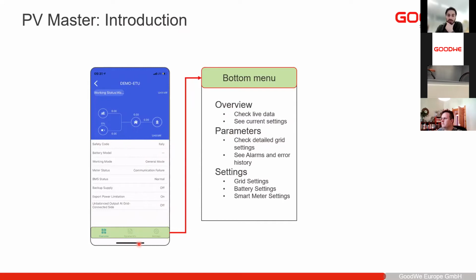Under parameters, you can check more details, what settings you have chosen, and you can also see the alarms and the history of the inverters. If anything happened, like there's a communication fault or grid fault or something, then it will all be saved here. On the right side, you have the settings, and this is where you set up the inverter, you do the commissioning, you set up the battery, and in case you want to change anything for the smart meter, the one we had here, then you also do it through the settings here.